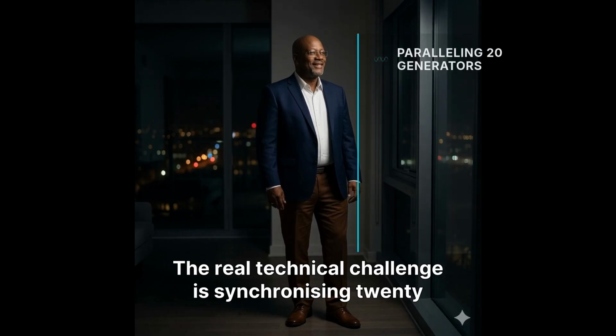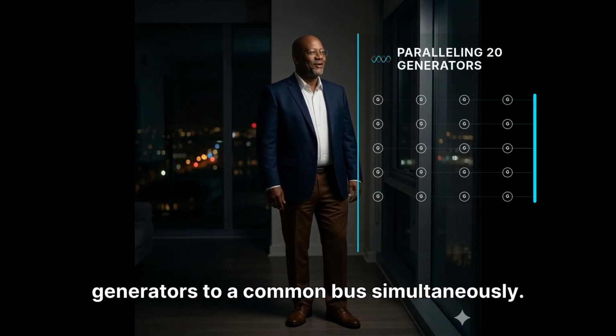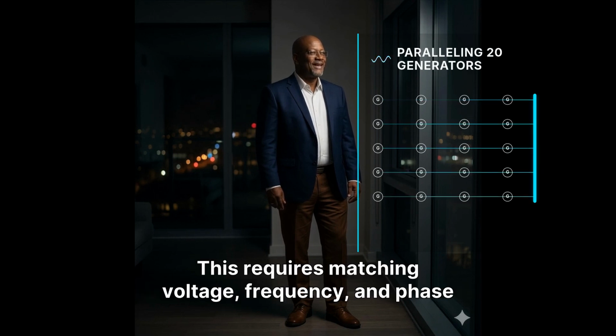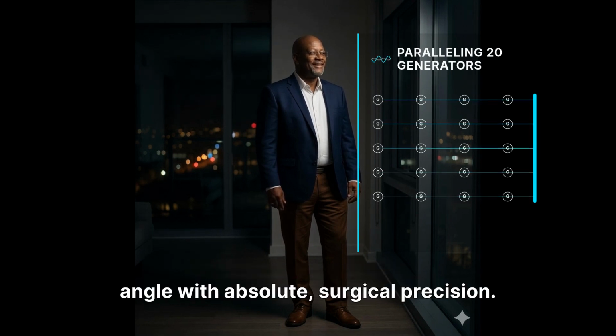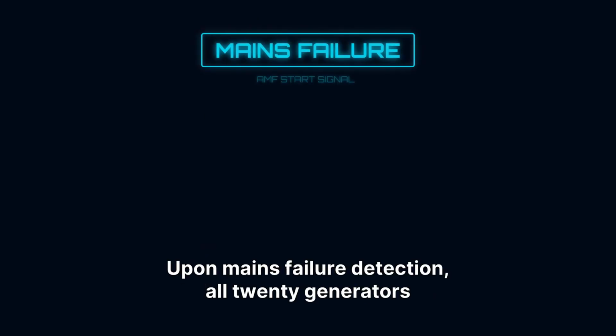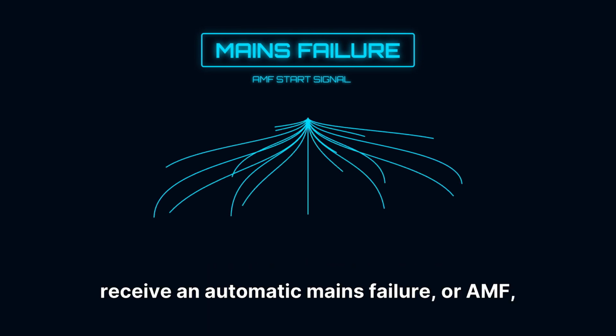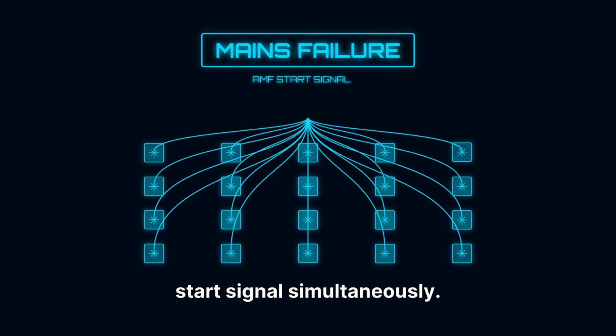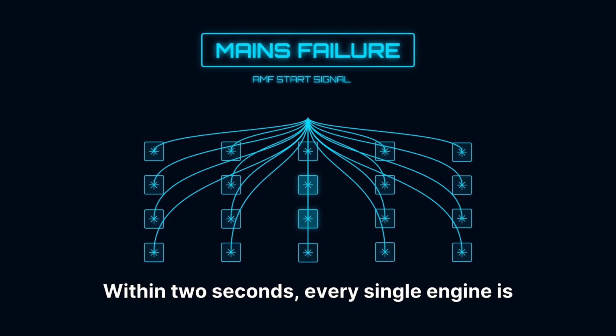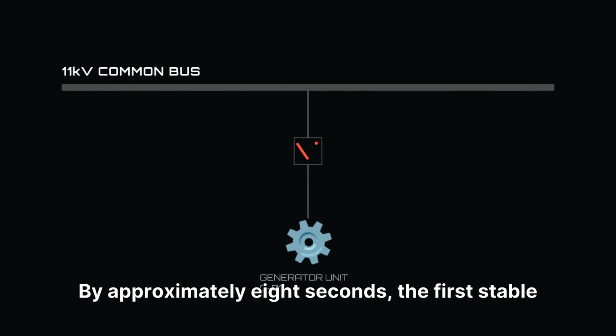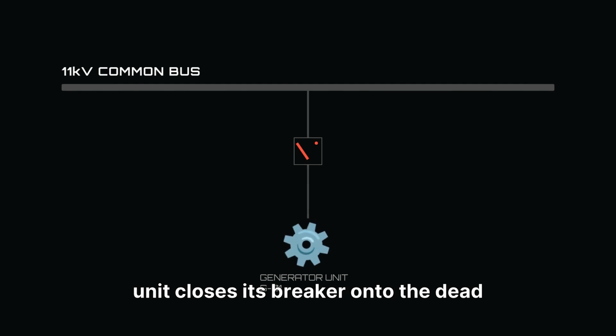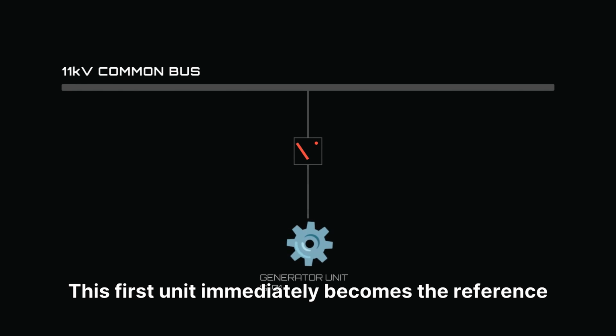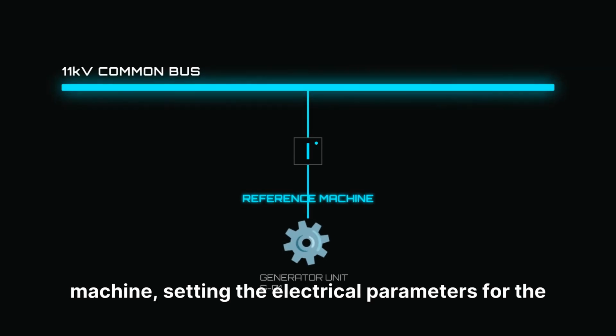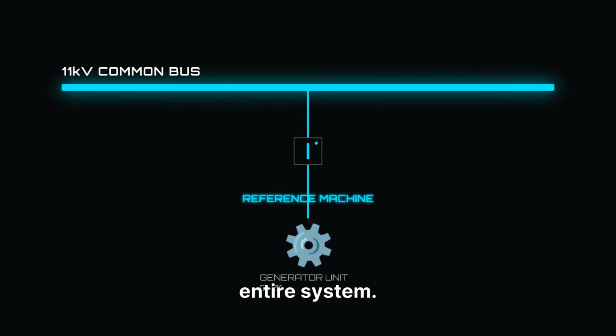The real technical challenge is synchronizing 20 generators to a common bus simultaneously. This requires matching voltage, frequency, and phase angle with absolute surgical precision. Let's look at the sequence. Upon mains failure detection, all 20 generators receive an automatic mains failure, or AMF, start signal simultaneously. Within 2 seconds, every single engine is cranking. By approximately 8 seconds, the first stable unit closes its breaker onto the dead 11 kV bus. This first unit immediately becomes the reference machine, setting the electrical parameters for the entire system.